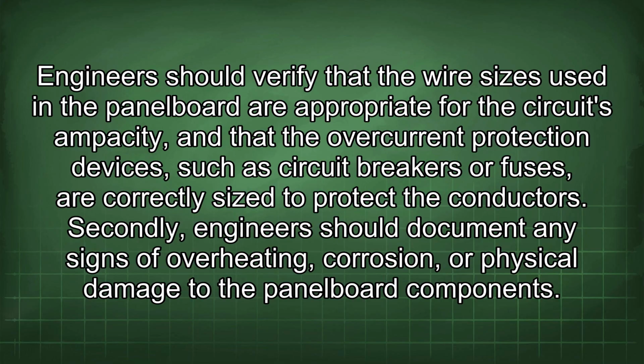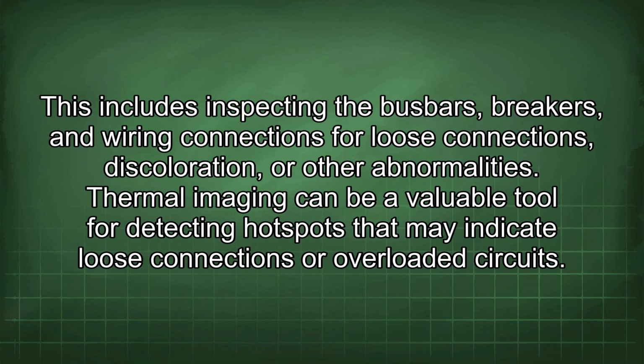Secondly, engineers should document any signs of overheating, corrosion, or physical damage to the panel board components. This includes inspecting the busbars, breakers, and wiring connections for loose connections, discoloration, or other abnormalities. Thermal imaging can be a valuable tool for detecting hotspots that may indicate loose connections or overloaded circuits.